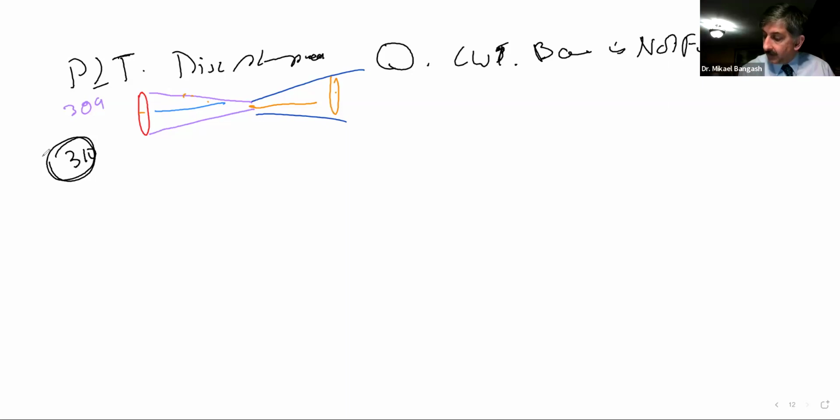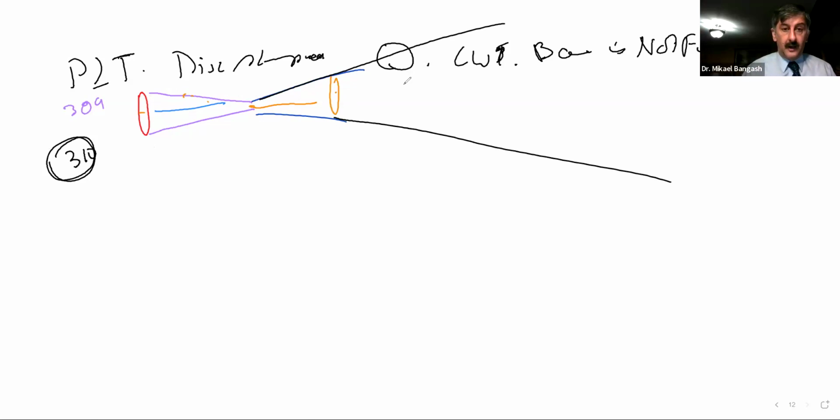Far zone. Oh, question, sorry. Question number 310. The far zone is the only region where the beam diameter exceeds the diameter of the transducer. And that's true. Because if we take the same beam here, it's going to keep on diverging. So from here and beyond, that's the only region where we'll find the diameter of the beam greater than the diameter of the PZT.